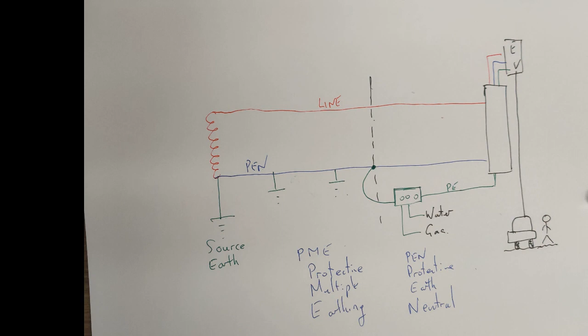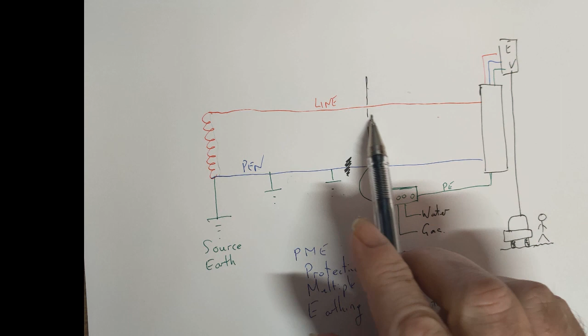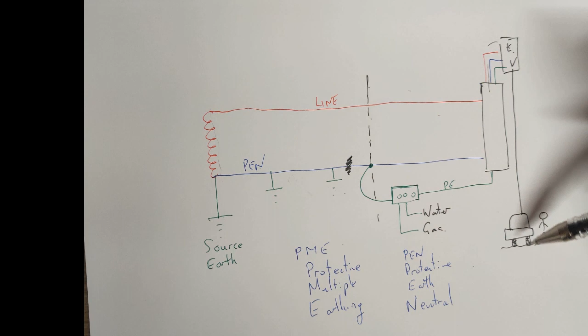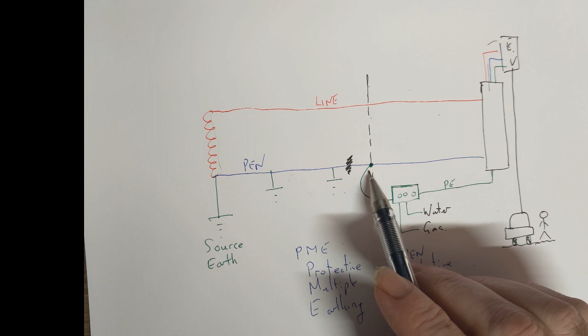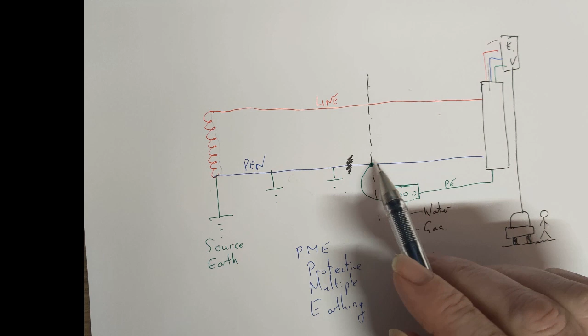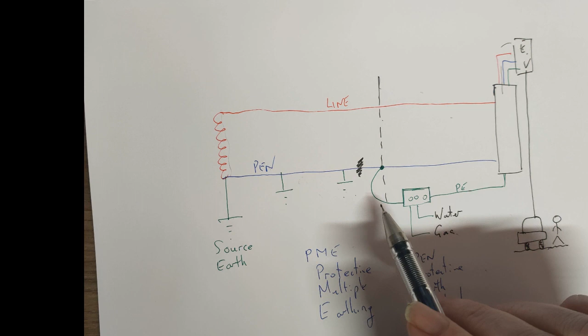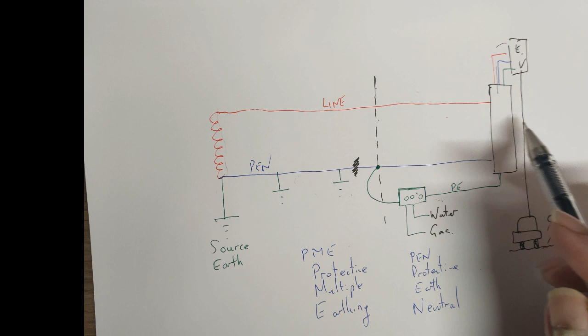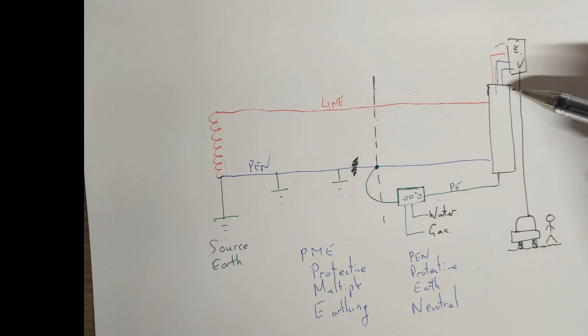However, what would happen if the cable was to break there? You'd have your 230 volts coming down your line, coming up into your EV charging unit, down to your car, and then going back along your neutral, along here. It's supposed to be coming along here, but it can't. Oh, but hang on a minute, I still have a route I can take.